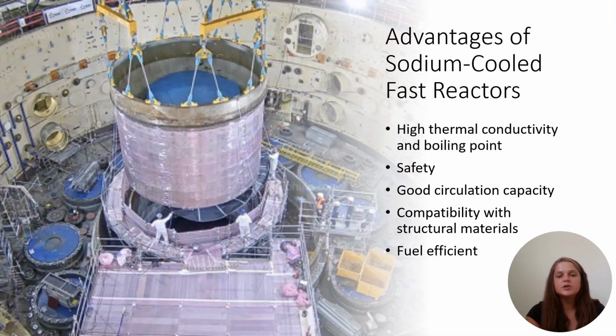Moving on to sodium-cooled fast reactors and their advantages. One of the main advantages of a sodium-cooled fast reactor is their high thermal conductivity and boiling point. So this results in a couple things. One of those things is it results in a flatter radial temperature profile within the pin and much lower normal operation and transient temperatures. This allows the reactor core to be designed with higher power density without the need to be pressurized.